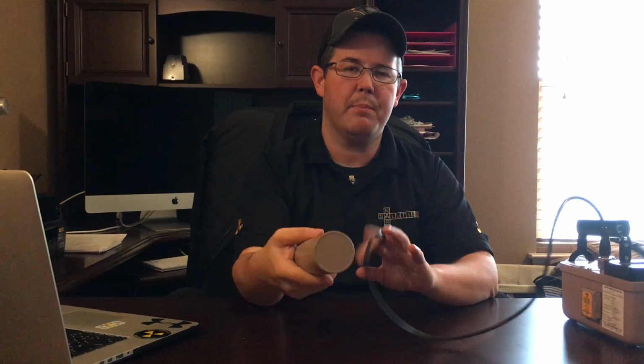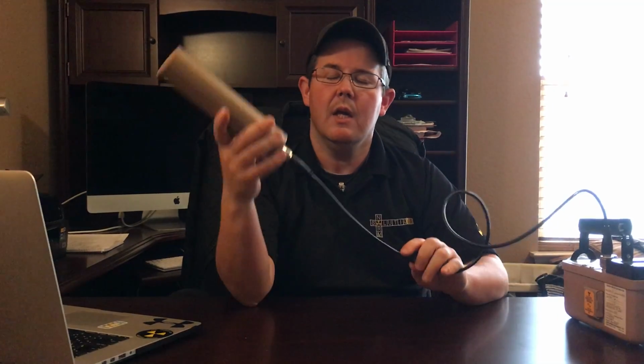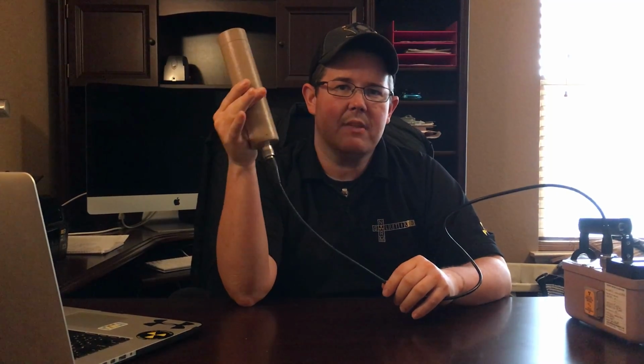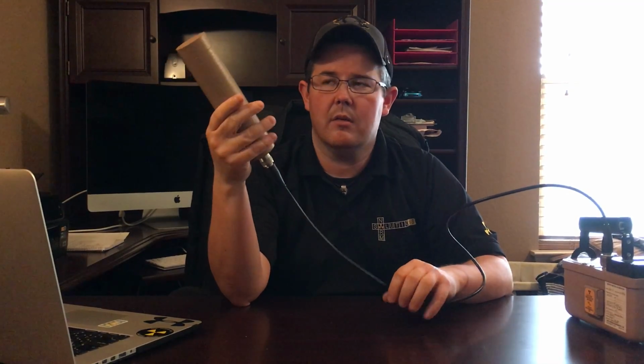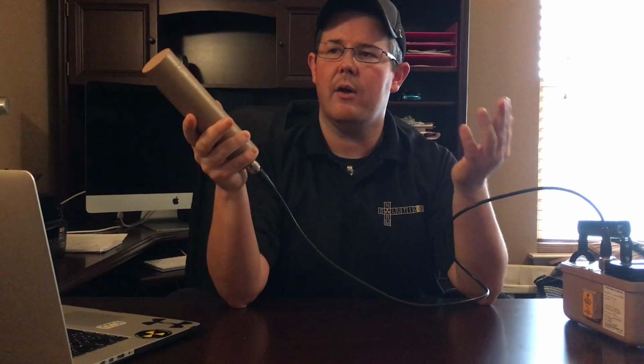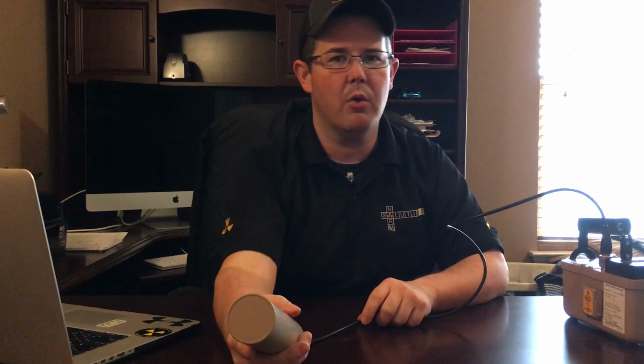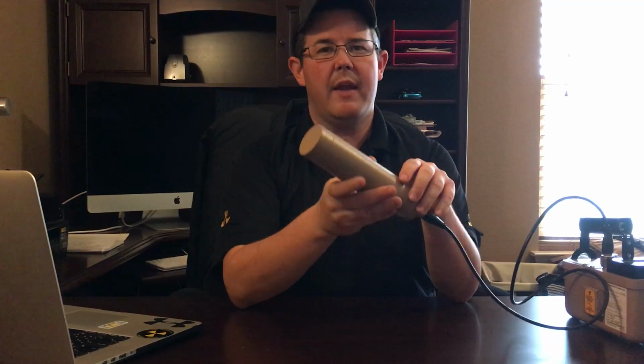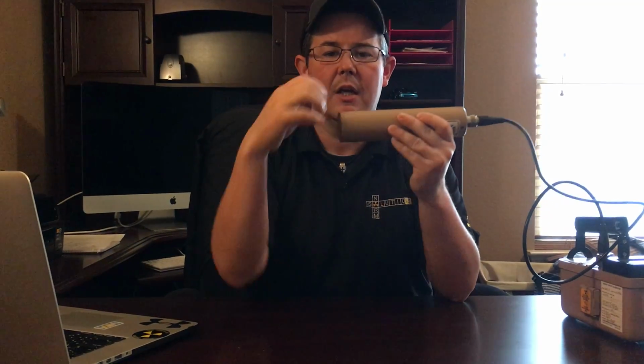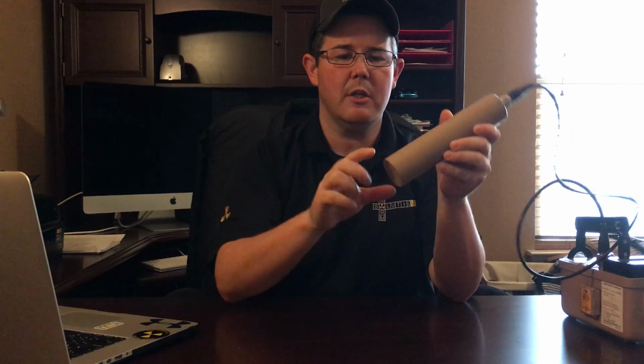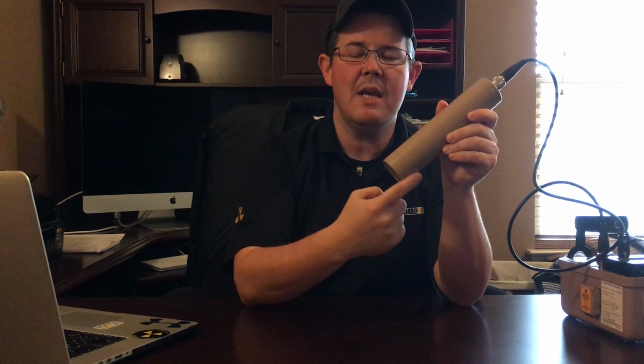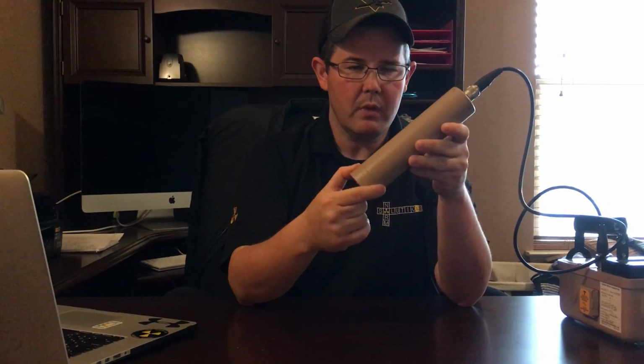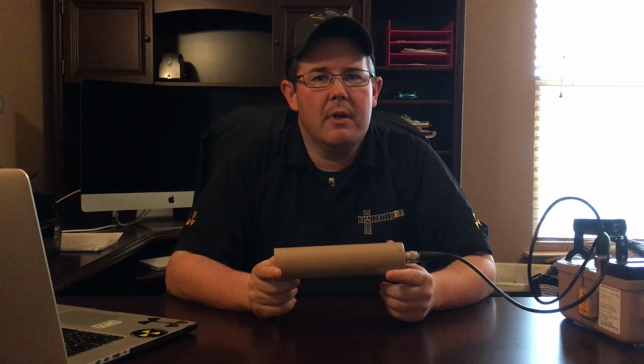When you're surveying, it is not always necessary to hold on to the probe and point it directly at the item that you're surveying. Now, in order to use this probe, I would actually have to have it within 1 centimeter of the object. Okay, so that brings up another concern. Well, now I do have to hold onto the probe and hold it on contact. That is not true. Ludlum did a really good job when they designed this probe, where you don't have to have it flush up against an object. You are actually allowed up to 1 inch. So this probe actually reads within 1 inch, okay? So it allows you a little bit of flexibility.